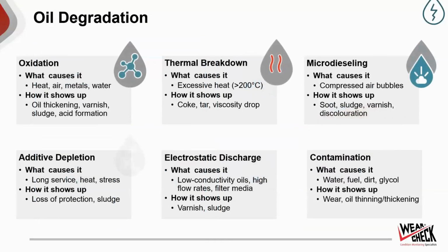Now, these degradation mechanisms all produce different types of identifiable physical and chemical characteristics that can be detected by oil analysis, either directly or through their byproduct or effect on the oil. So for example, in the case of oxidation, this would reveal itself with an increase in viscosity, an increase in acid buildup and sludge formation, as well as a reduction of the total base number or alkalinity reserve of the oil. So that's just one example. So by understanding these degradation modes and knowing what to look for, we can catch problems early and extend the life of both the lubricant and ultimately the asset that it's protecting.